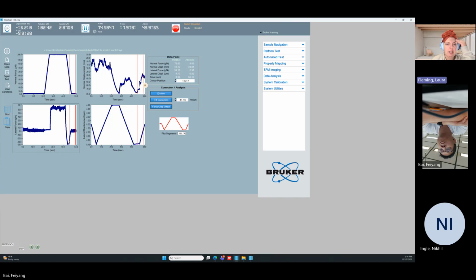So this is not a great example, but sometimes I would argue that this is probably the normal displacement here at the end of the test, which is about 30 nanometers versus 0 at the beginning. So we probably scratched like a 30 nanometer scratch into the sample. That's probably what's left on the sample surface. So you can go through and get that kind of information, right? You can look at what happened and at what points.